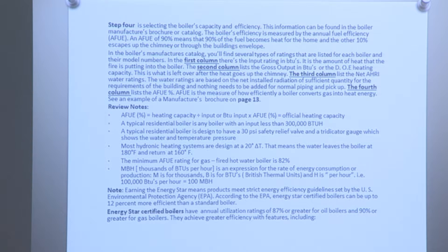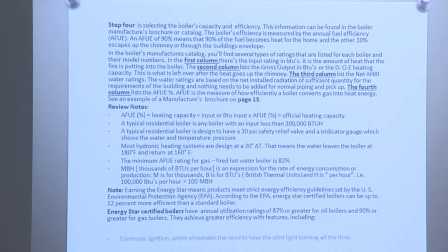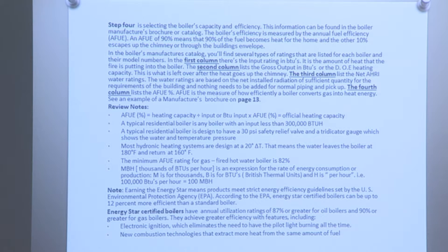Earning the Energy Star means products meet strict energy efficiency guidelines set by the U.S. Environmental Protection Agency. According to the EPA, Energy Star certified boilers can be up to 12% more efficient than a standard boiler. Energy Star certified boilers have an AFUE rating of 87% or greater for oil boilers, or 90% or greater for gas boilers. They achieve greater efficiency through features including electronic ignition — eliminating the need for a pilot light — new combustion technologies that extract more heat from the same amount of fuel, and sealed combustion that uses outside air to fuel the burner, reducing drafts and improving safety.